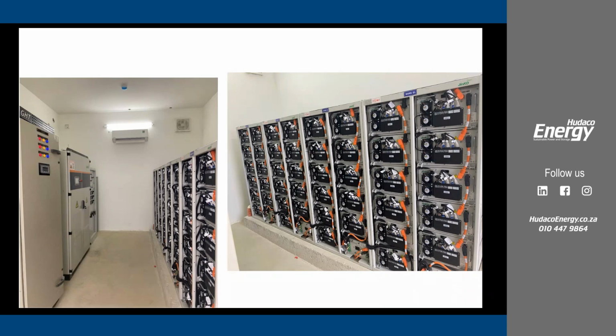So there is no DC-DC. You can see the batteries on one end, the different racks from bank number 1, 2, 3, 4 to make 135 by 4, that is 540 kilowatt hours, with all the batteries and connections made. Then we have the PCS on this side. Then we have the DC combiner cabinet, with the BMS and the screen that I mentioned. Then this is the AC combiner box. Then they provided the cooling system, with these fans and the air conditioning units as well.